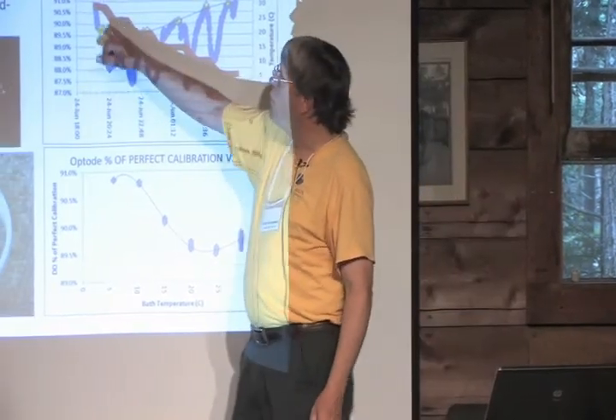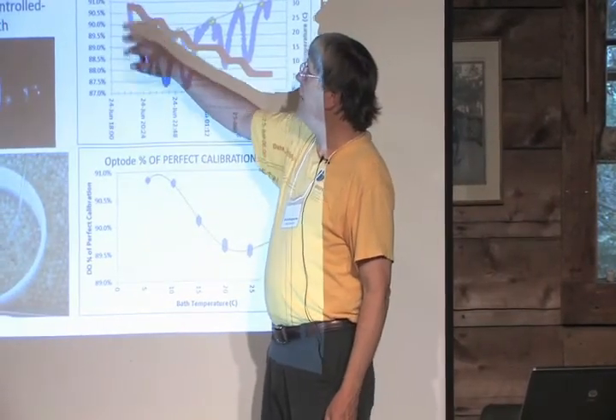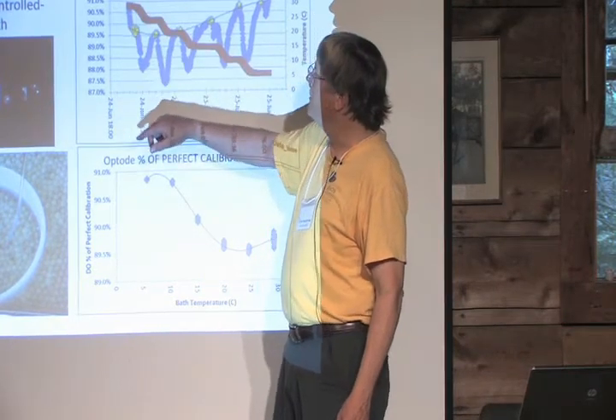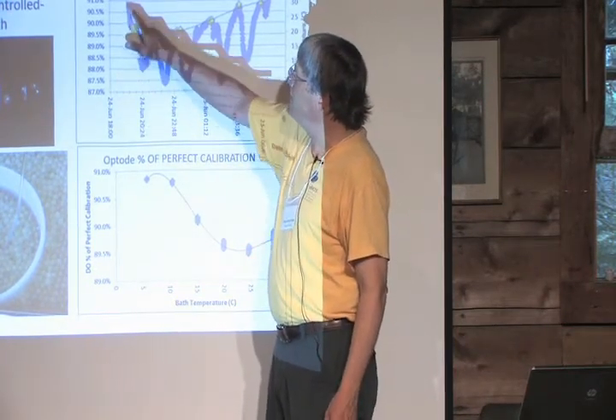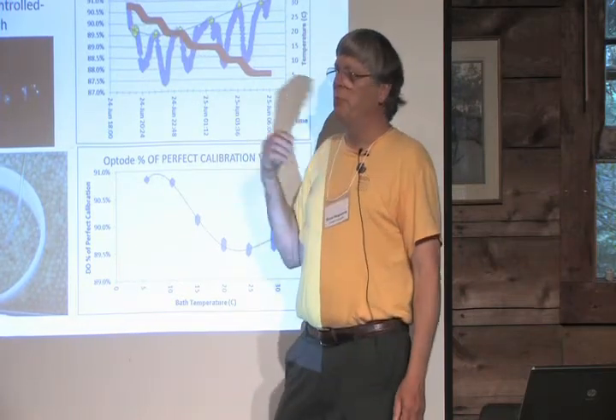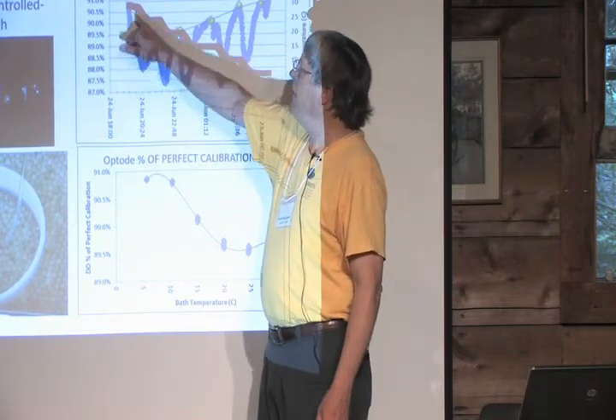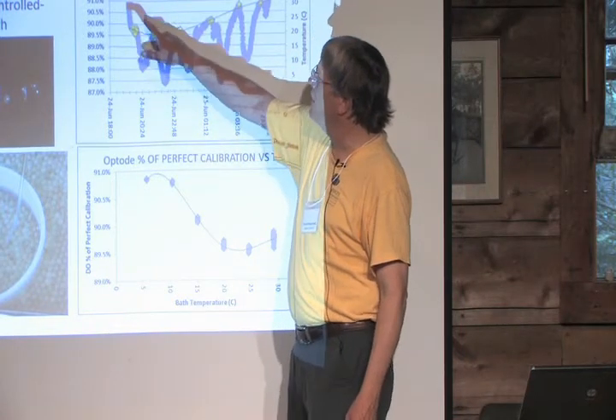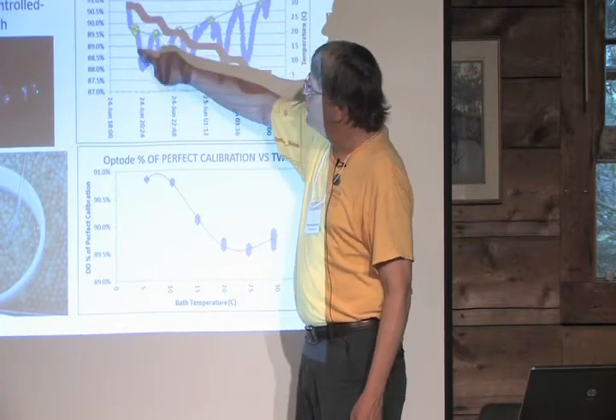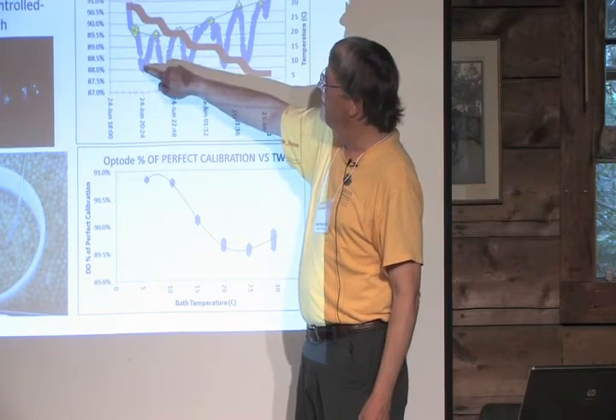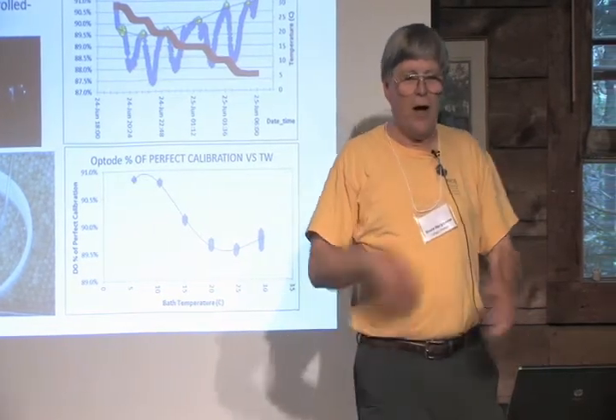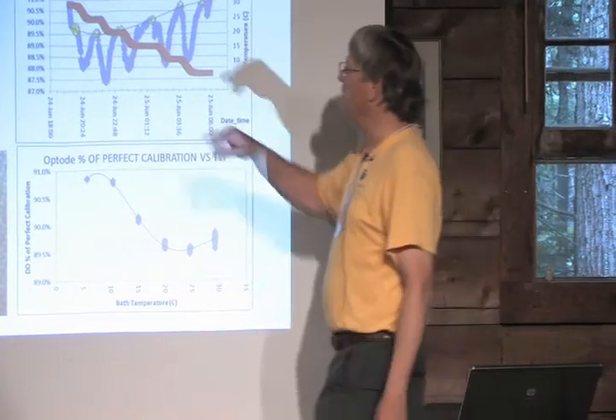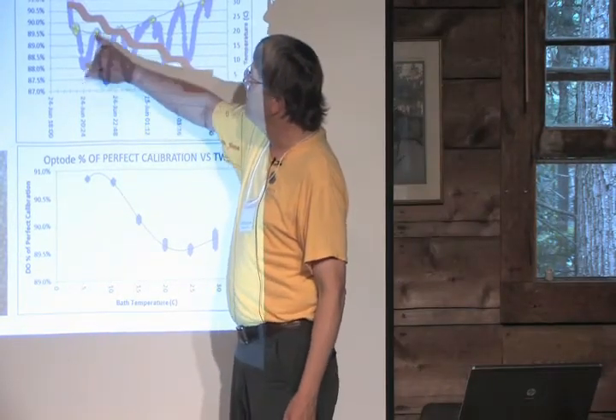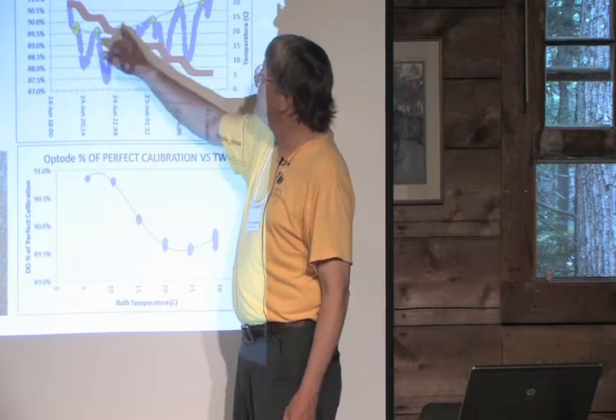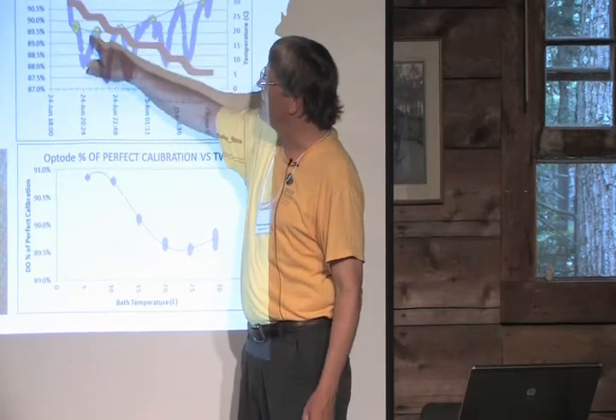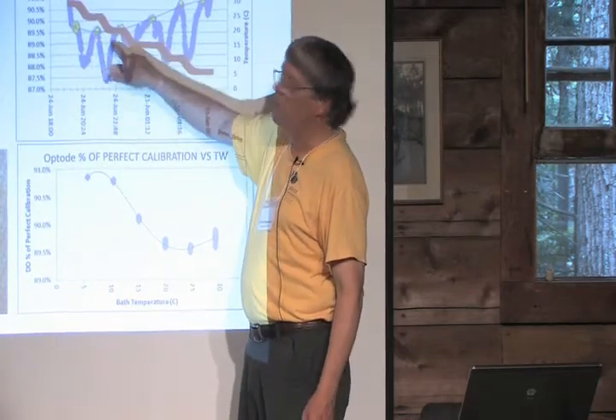And I started out with warm water that was bubbled, and I kept the temperature at 30 degrees until the oxygen leveled off. And here's the pressure-corrected oxygen level at 30 degrees, these yellow points. And then I lowered it by 5 degrees. The oxygen dropped because of the drop in temperature, and then oxygen started being added back in by the bubblers to reach the new equilibrium, so it came back up again. Once it reached that, I lowered the temperature. So these are successive equilibrium points. These are the artifacts. If you don't wait long enough, you get the wrong answer.